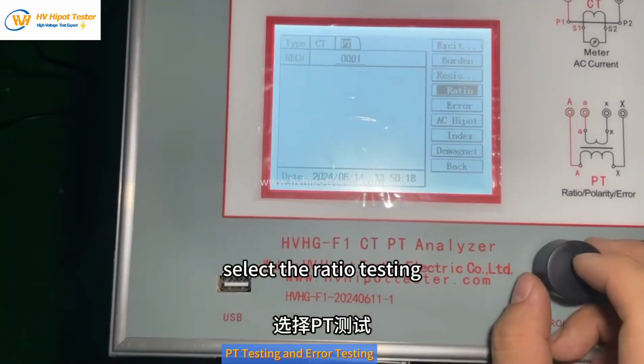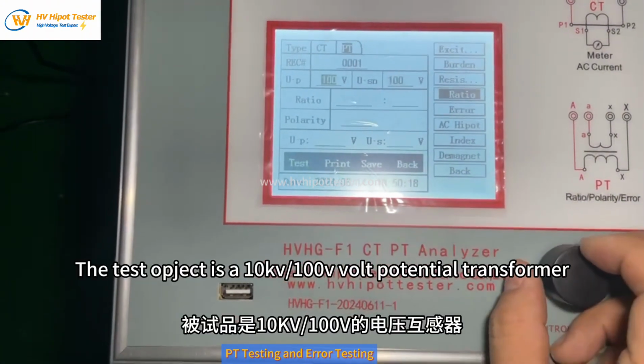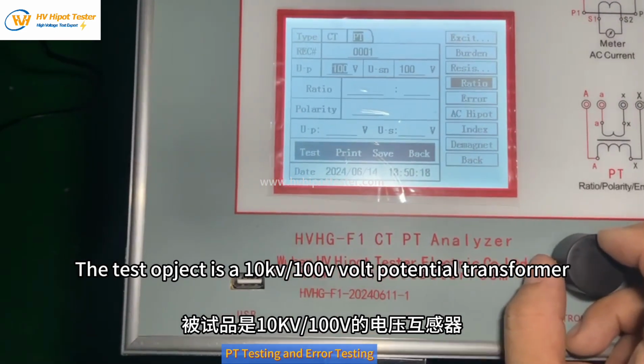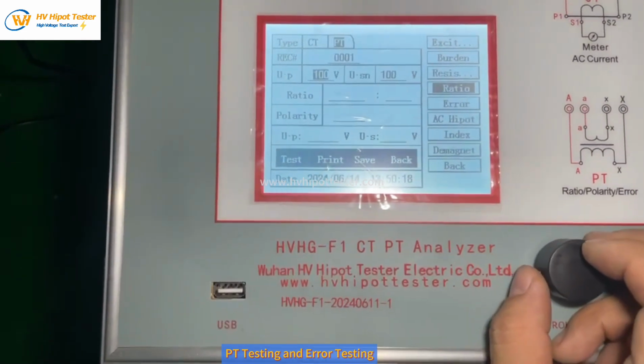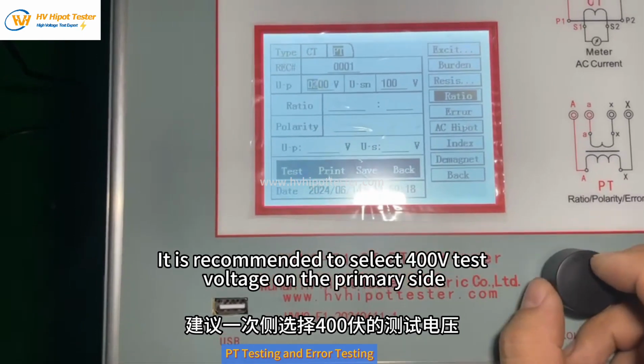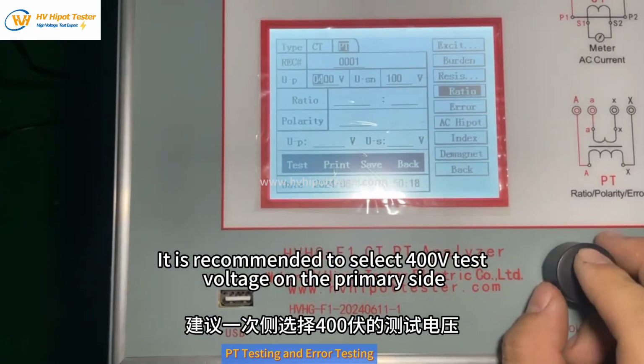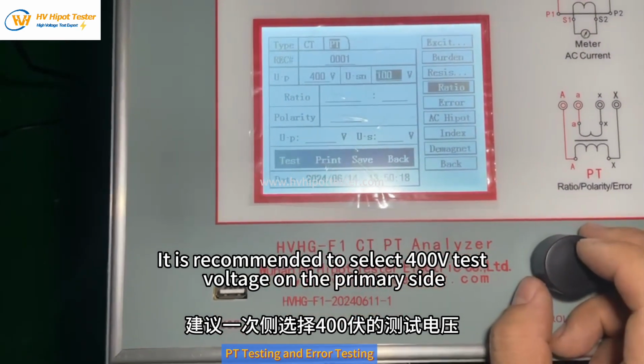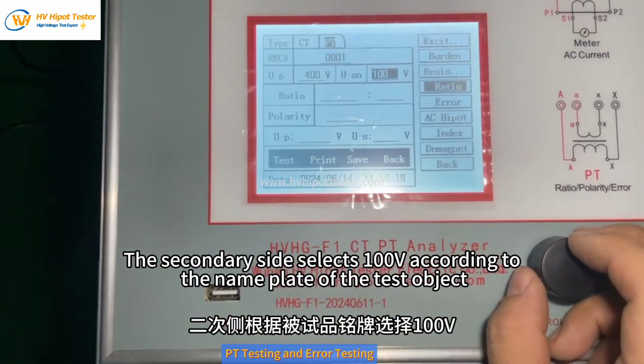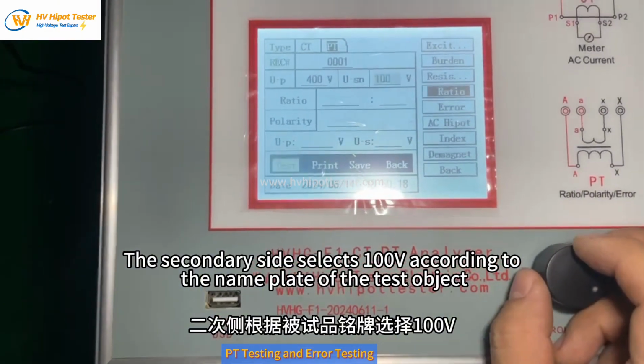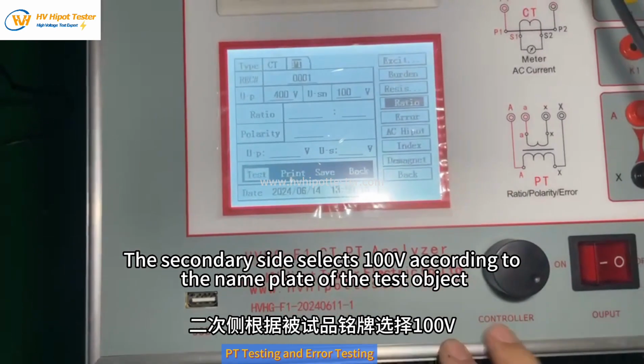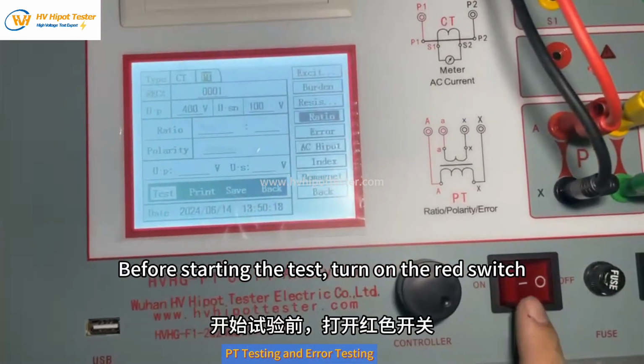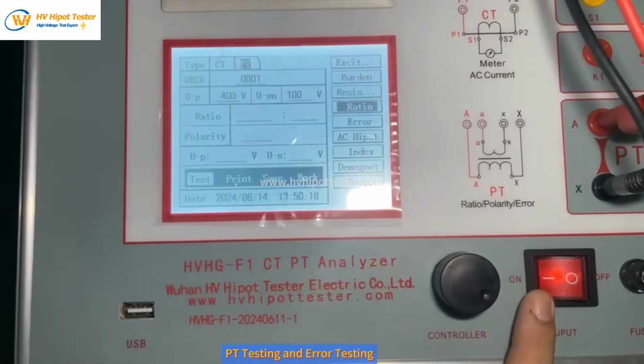Select the ratio testing. The test object is a 10 kV 100 volt potential transformer. It is recommended to select 400 volts test voltage on the primary side. The secondary side selects 100 volts according to the nameplate of the test object. Before starting the test, turn on the red switch.